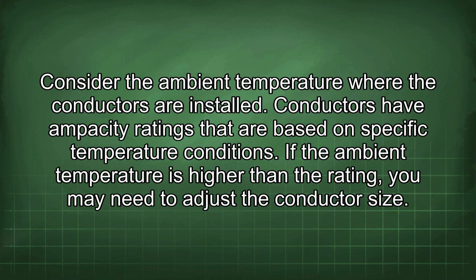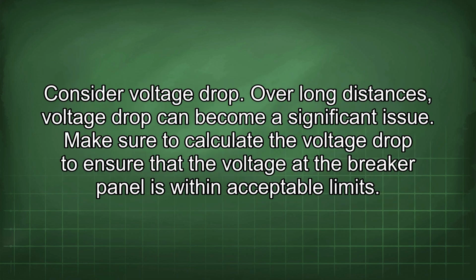Consider the ambient temperature where the conductors are installed. Conductors have ampacity ratings that are based on specific temperature conditions. If the ambient temperature is higher than the rating, you may need to adjust the conductor size. Consider voltage drop. Over long distances, voltage drop can become a significant issue. Make sure to calculate the voltage drop to ensure that the voltage at the breaker panel is within acceptable limits.